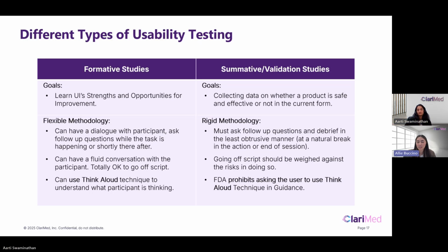As far as formative studies, I also want to point out that these can be used at a bunch of different stages in development. So as well as just finding the use errors with the existing design, you can also use them to guide your design and hopefully make a more usable product. So for example, for IVDs, if there's a sample collection process where they need to add the sample to a dilution buffer or something, some sort of sample manipulation happening, you can use formative studies to figure out what is the easiest way for lay users, for example, to do that.